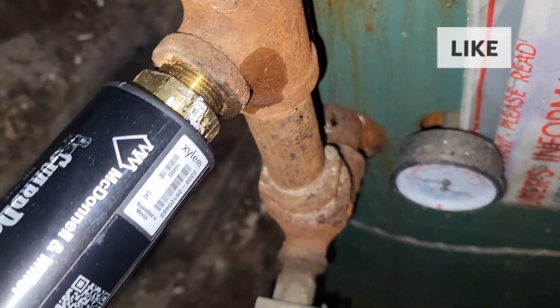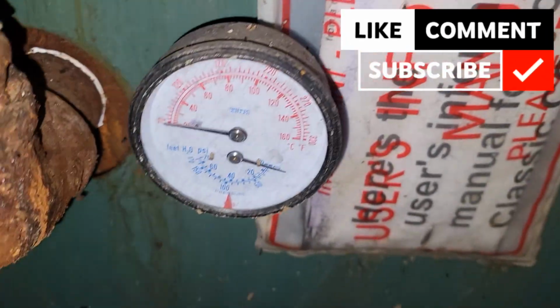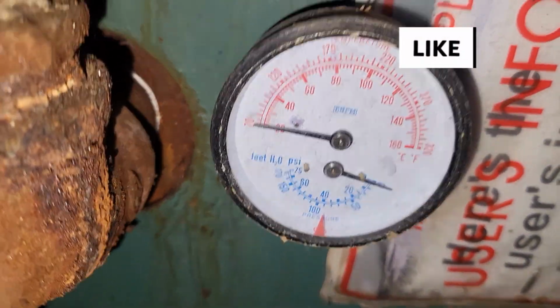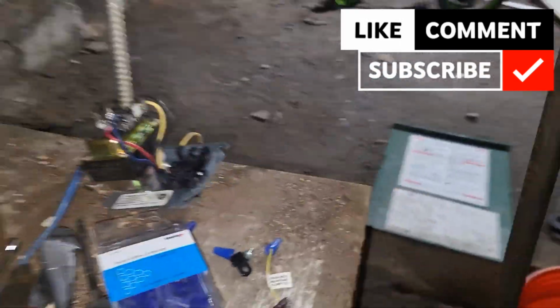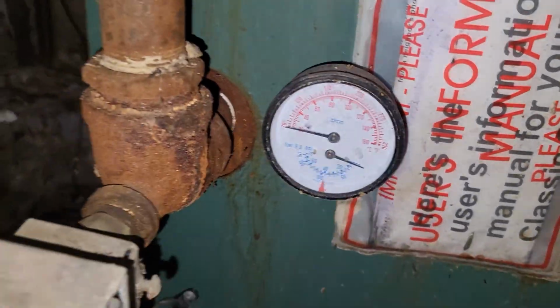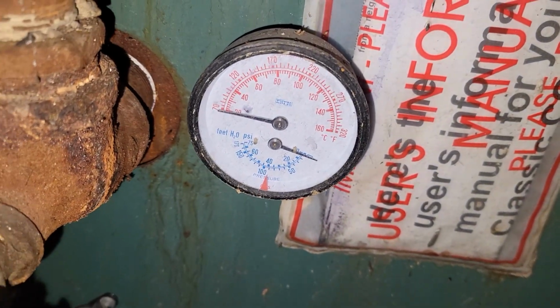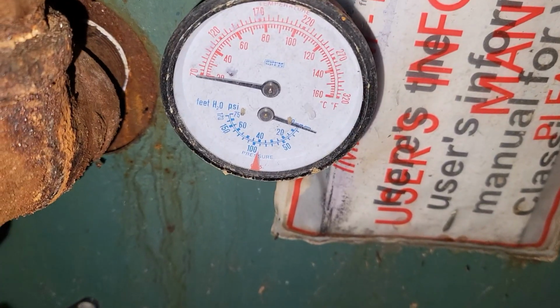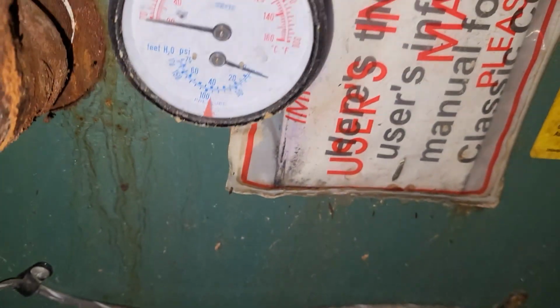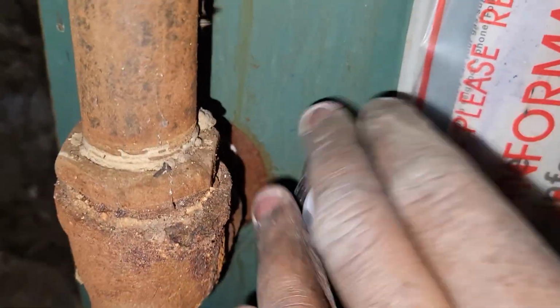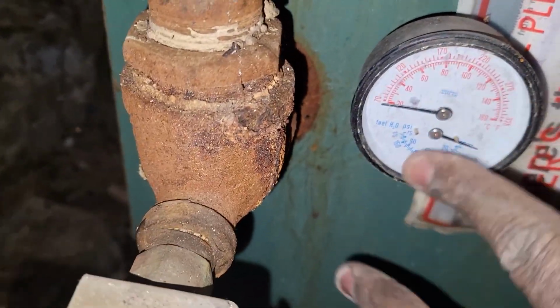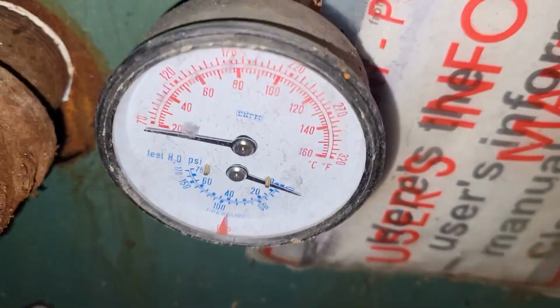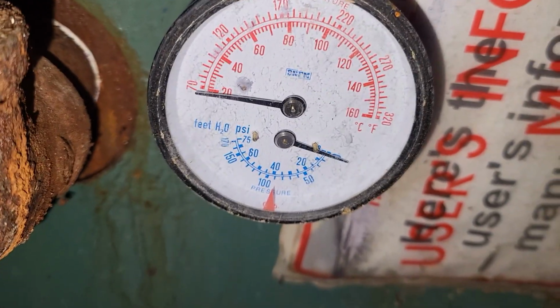Guys, I got my low water cutoff installed. Right now I'm just leak testing. I got my fan center in. And they don't have an aquastat, they just have an inline limit switch here. And that's already preset at 180. This is an older boiler, but all the controls are still operating. Everything looks okay, nothing's banged up too bad.